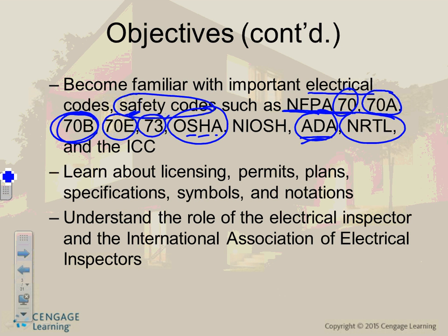This one is the Nationally Recognized Testing Laboratory. Those guys take a switchgear and say, okay, this is 4,000 amp. They put 4,000 amp through it and blow it up, and they say yep, it can handle 4,000 amp for 5 seconds. So those are UL, you guys are familiar with them. UL can put a label on everything. So if you've got the UL label, it means they've blown up a couple of them to validate the product you're looking for. Very, very important concept.